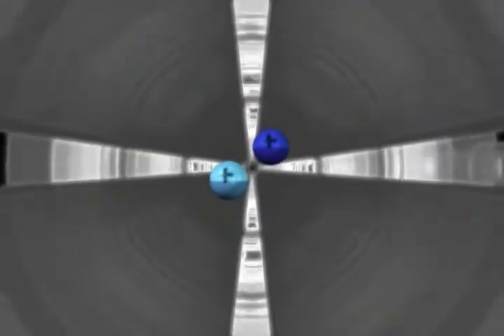What we found with the newer technology is that we were getting better desolvation and therefore better ion generation. We were able to get more ions into the detector and therefore reduce our background noise by increasing the total number of ions that we put into the detector, which gave us significant increases in sensitivity. The improvement in the ion generation process allows us to see those low parts per trillion that we've so much desired to see over the last 10 years. Very visible now with minimal background issues, primarily because of the changes in the source design, allowing that ion to transition without causing any destruction of our analyte on the way.